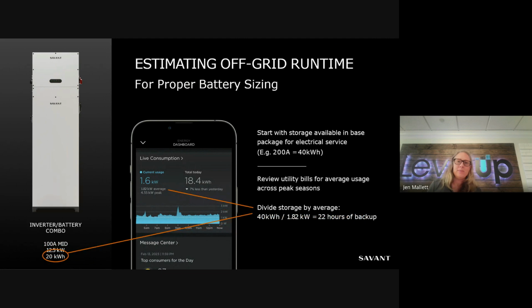As we look at estimating off-grid runtime, which is the question of, okay, how long is my home battery going to last, and how long is my off-grid runtime? As we mentioned earlier, there are a lot of different components as part of that. But we look at dividing the storage by the average. So if you've got essentially 40 kilowatt-hours and you're taking that 1.82 kilowatt calculation that we had earlier, you're looking at about 22 hours of backup, right?